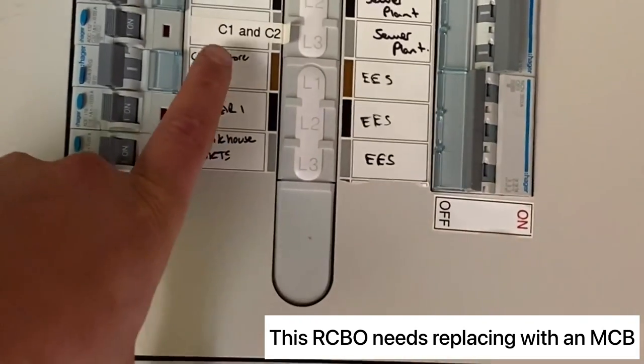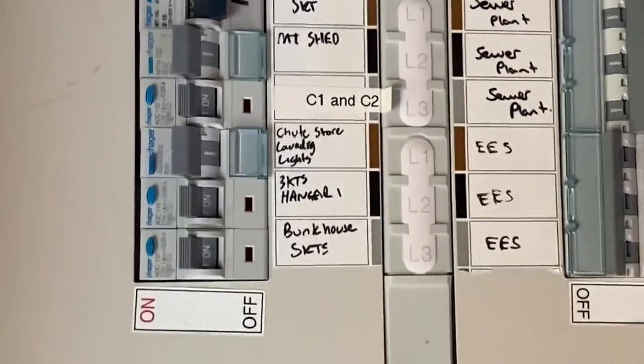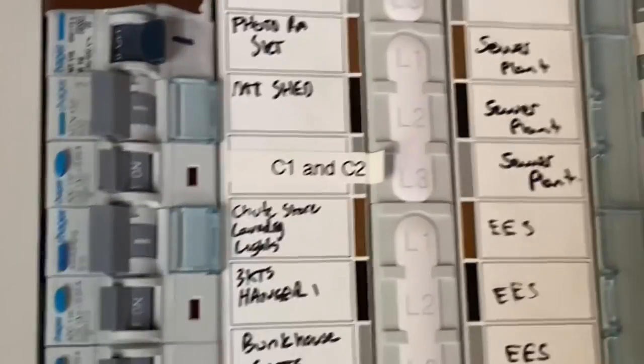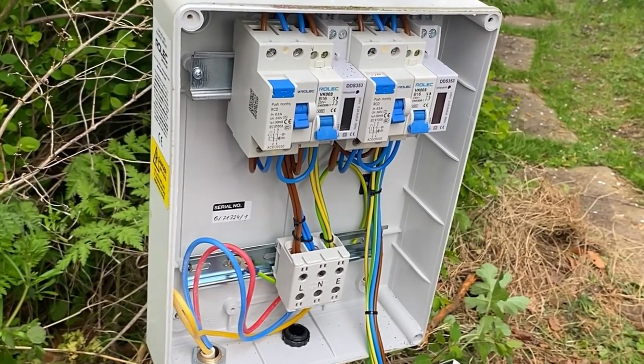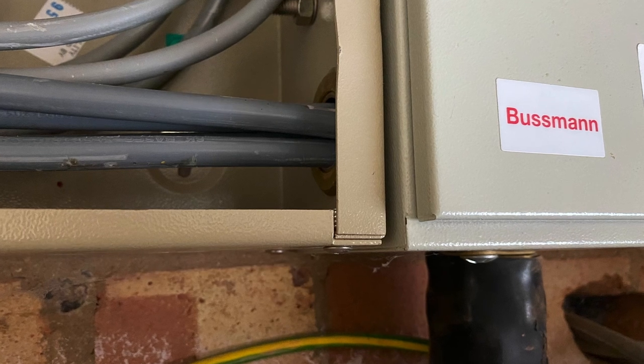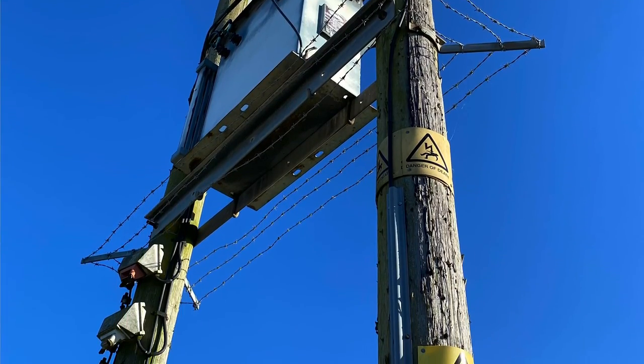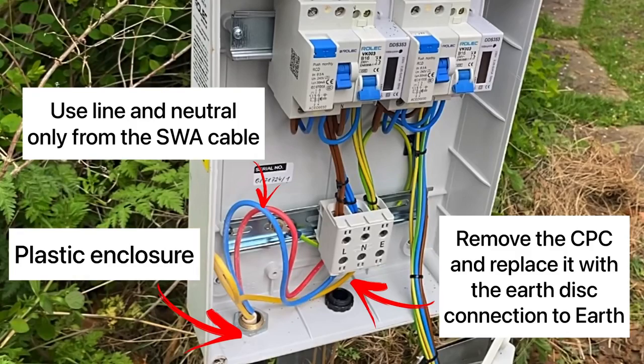Very confusing when doing rectification work off the back of an EICR, because C1 and C2 are classification codes — but we worked out they actually meant caravan one and caravan two. What's happened is they've taken an RCBO in this main distribution board and run it to two caravans with no earth stake or alternative means of earthing. The PME has been exported, which could be an issue if we have a loss of the PEN conductor, potentially making the chassis of these caravans live.